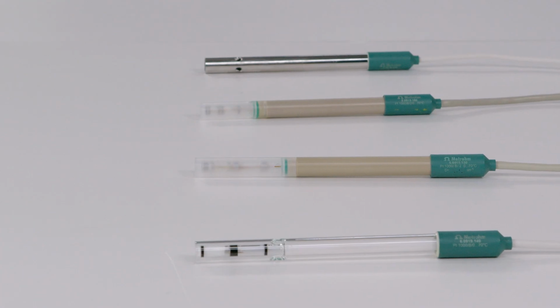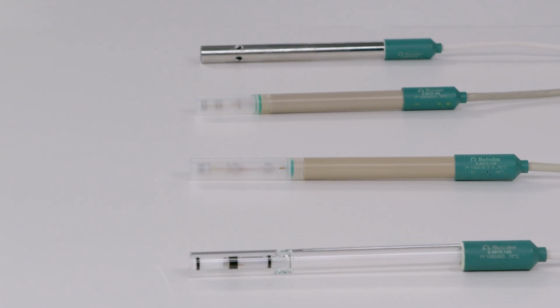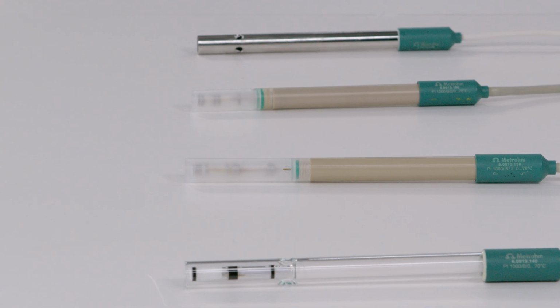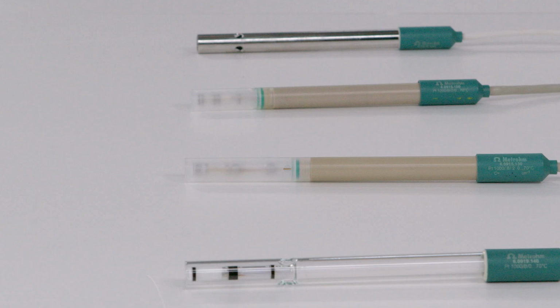While conductivity sensors are generally robust, factors like contamination or slight changes in electrode geometry over time can affect readings. Calibration determines the precise cell constant of a specific measuring cell, compensating for any deviation from its ideal value. The cell constant is unique to your sensor and relates the measured conductance to a specific conductivity.